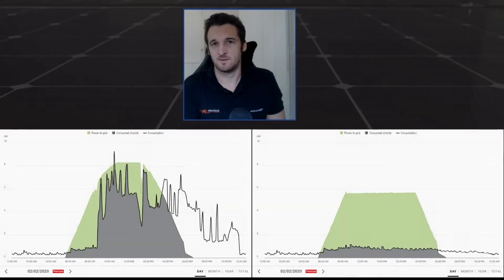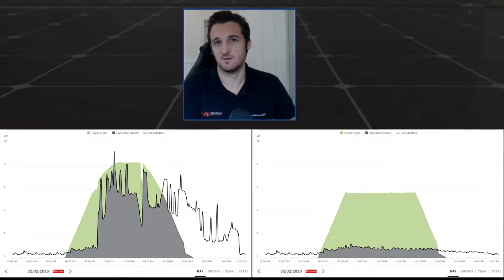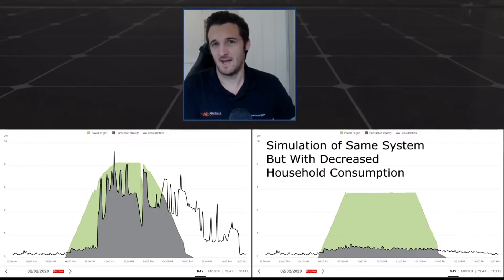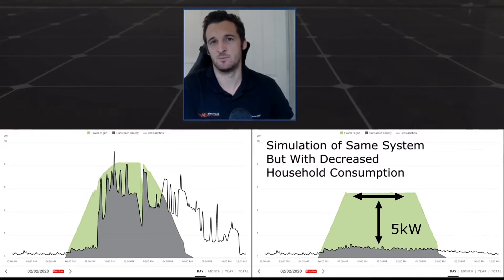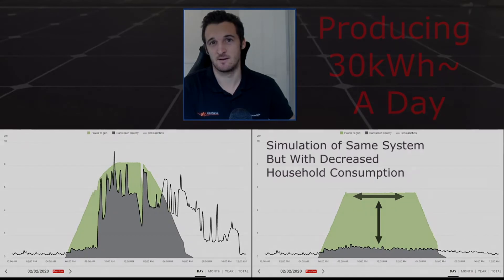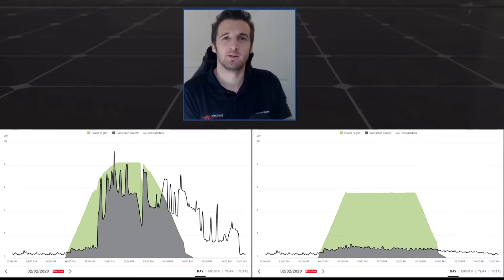Potentially the biggest mistake — and what we're seeing in a lot of quotes unfortunately — is just going to 10 kilowatts for the sake of it. Homeowners are either not understanding it or it's not being explained properly in the quoting process, but if you're getting 10 kilowatts and export limited to 5 kilowatts, that means you need a pretty excessive base load of 5 kilowatts so nothing is wasted. As an extreme example, the image to my right shows the same system but without the same consumption profile. You can see a hard flat line at just above 5 kilowatts because it's limited to that 5 kilowatt export — you've paid for a 10 kilowatt system but your usage is limiting you to much the same result as a 5 kilowatt system. On paper it looks good but in reality you could have paid half the price and had the same outcome. Although you can have 10 kilowatts, it's not for everyone — it requires good analysis of the bill and your power usage to determine the right size.